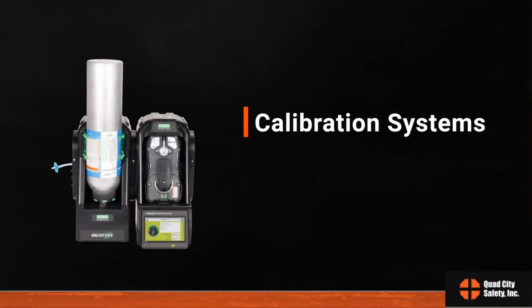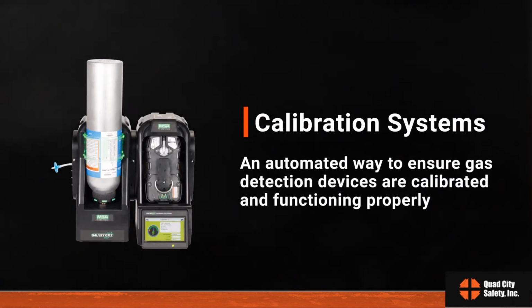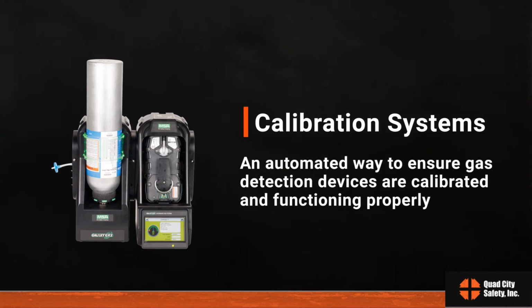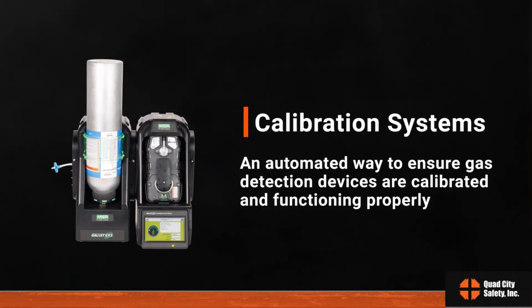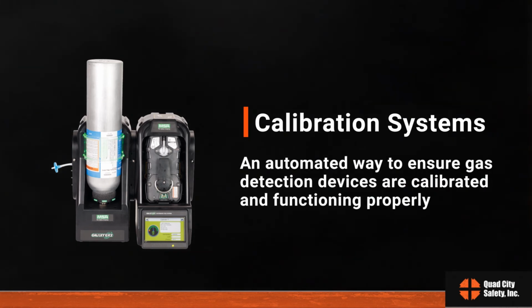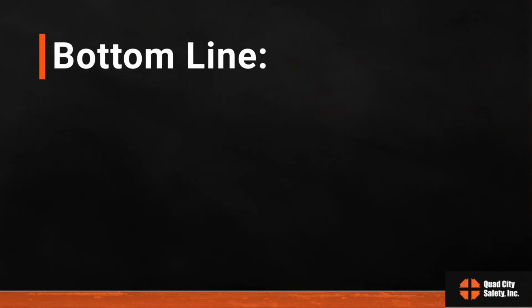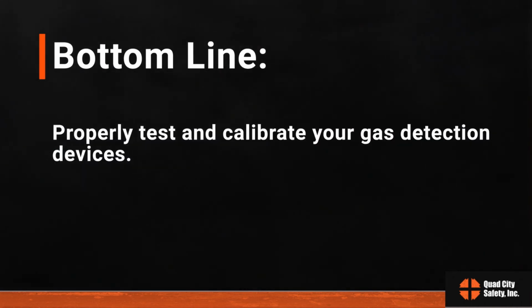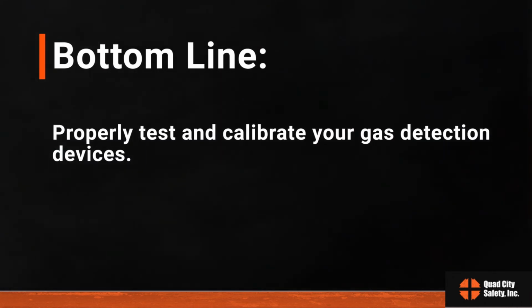Calibration systems are a great investment. They provide an automated way to ensure gas detection devices are calibrated and functioning properly. From collecting information and logging important data to sending email alerts, these simple-to-use systems take human error out of the device calibration equation. The bottom line, like checking your smoke detectors at home, properly testing and calibrating your gas detection device is crucial to the health and safety of those who rely on them.